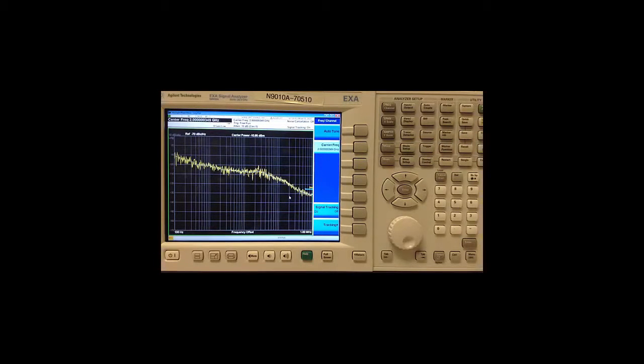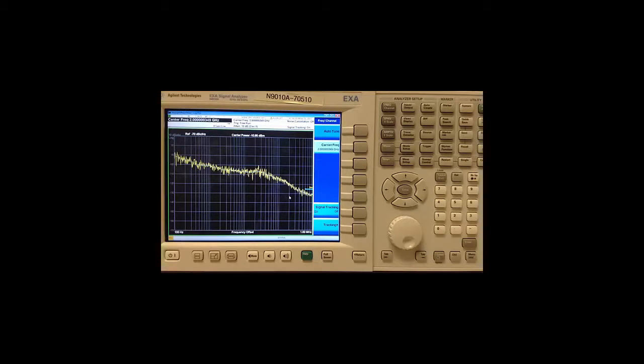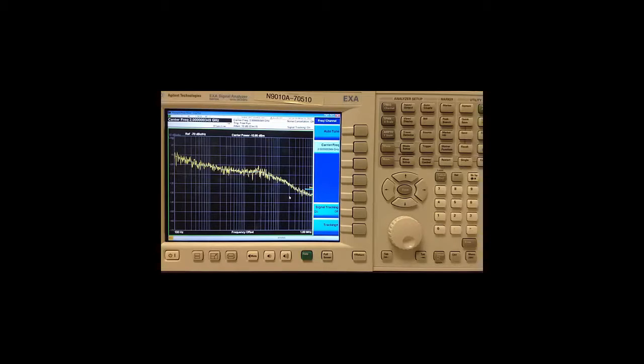This is the most common display used for measuring phase noise, where the single sideband phase noise is displayed in dBc per hertz versus offset frequencies from the carrier. If the carrier is minus 50 dBm or more in power, the analyzer can auto-tune to it.